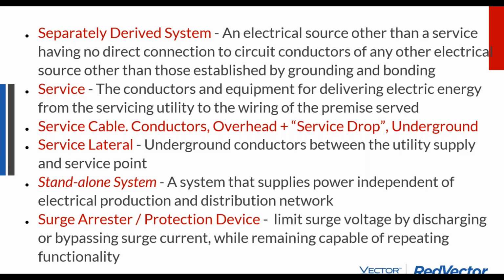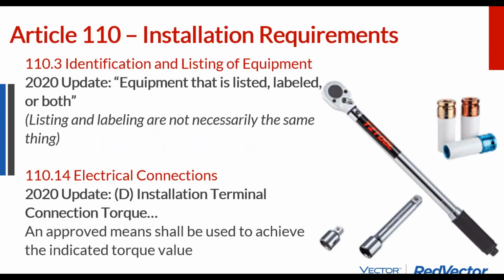Let's see. Some general definitions. This is a change to the electric code, and 110.14 is the bottom ones that I'm talking about. The installation terminal connection torque. It says an approved means shall be used to achieve the indicated torque value.